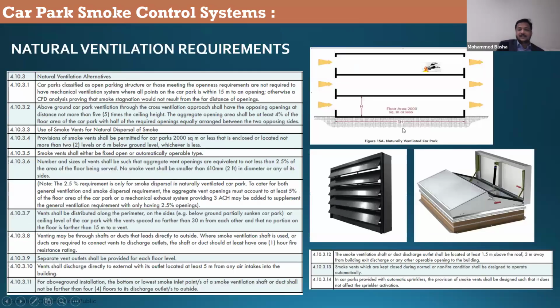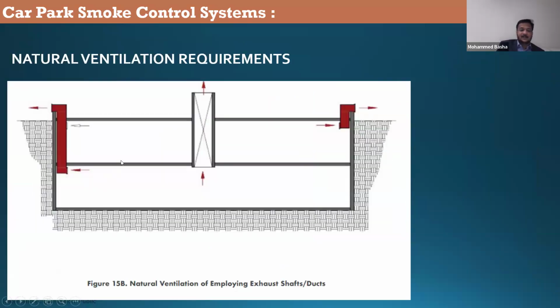Natural ventilation. Okay, I do not want to go into full depth, as you people are very well aware of the QCD requirements. So this is the natural ventilation arrangement, how it should be. The smoke vents are to be provided at the top. How are the smoke vents to be provided? Like this. This is how, for underground car parks less deep than 6 meters and less than 2000 square meter area, you can have such arrangements. This is a reference from NFPA, QCDD.